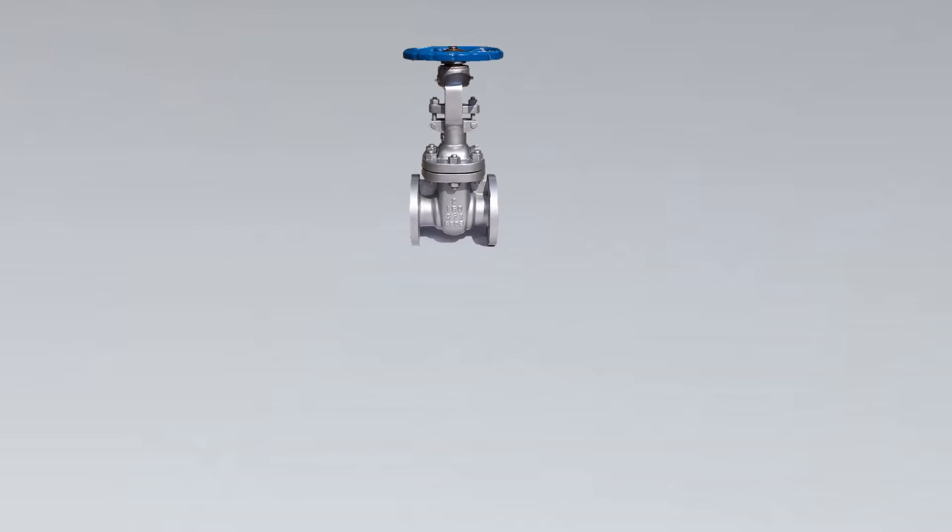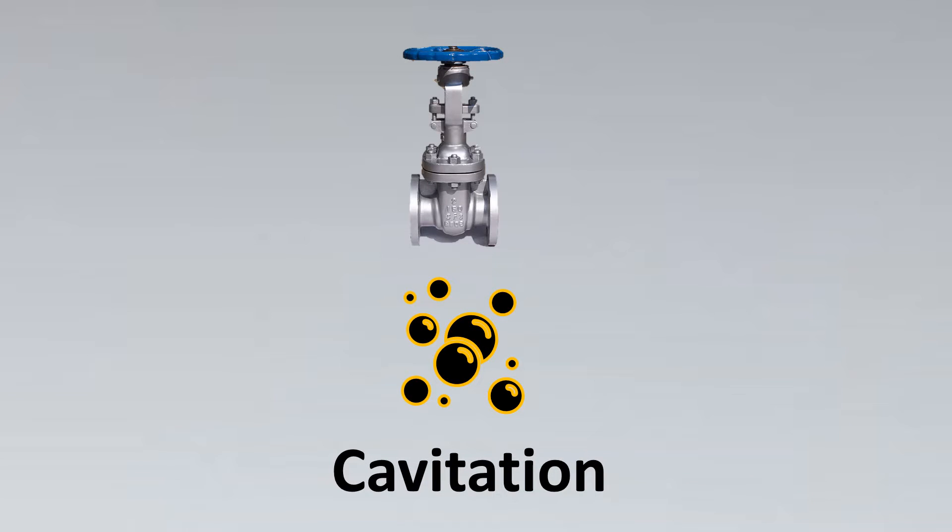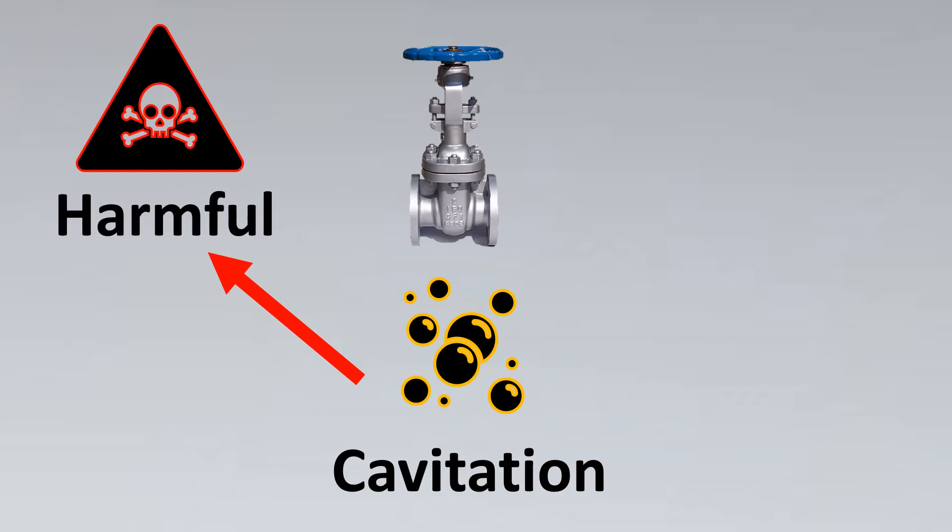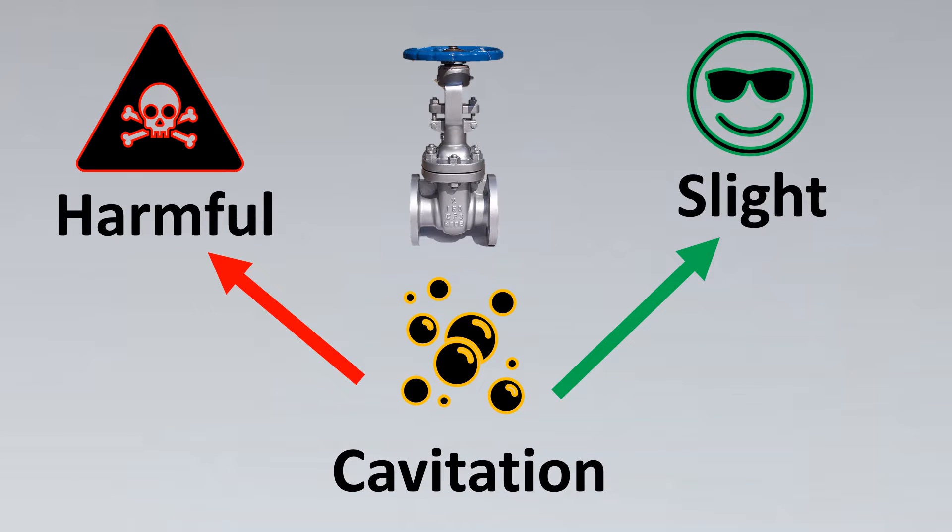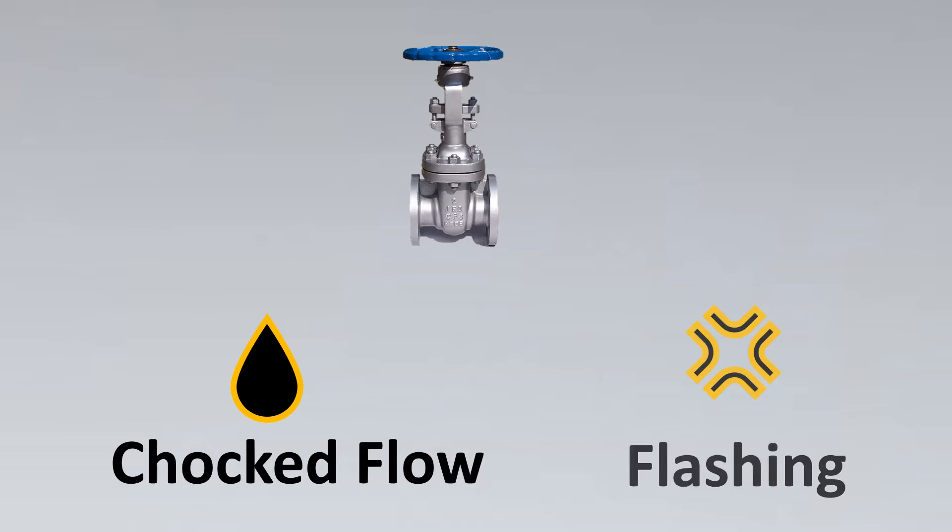If it's a control valve and cavitation is happening, the sigma value, which is also called the cavitation index, can help us identify whether it's harmful cavitation or very slight cavitation that we can easily handle. It also helps us to know whether the flow is choked flow, whether there's flashing, and what precautionary measures we can take against it.